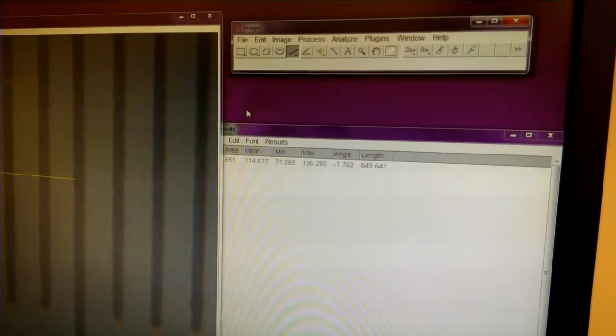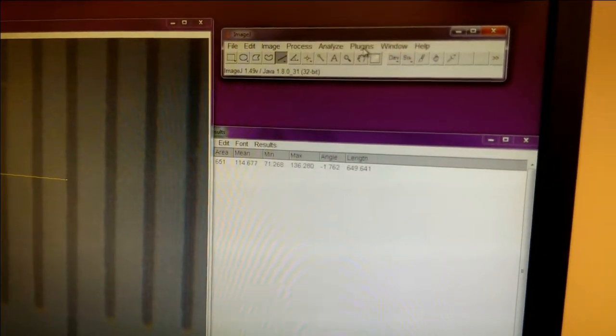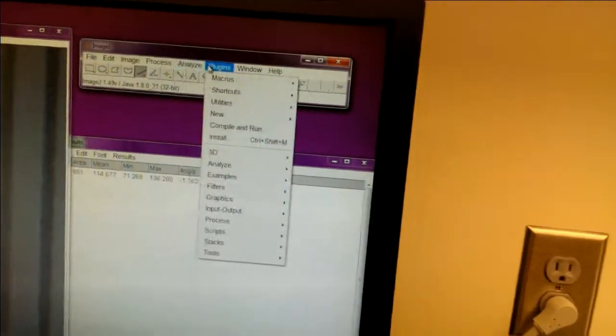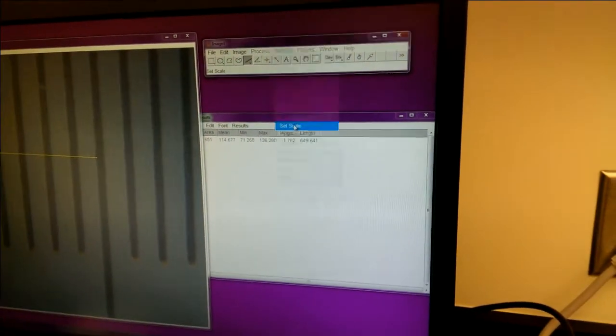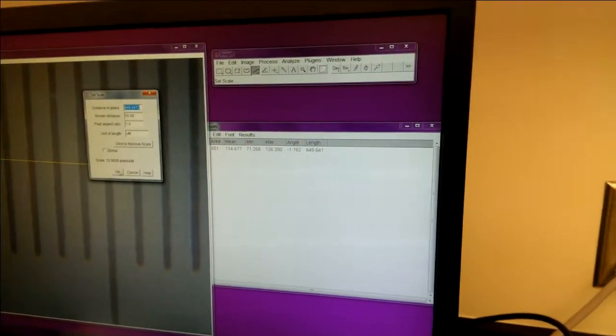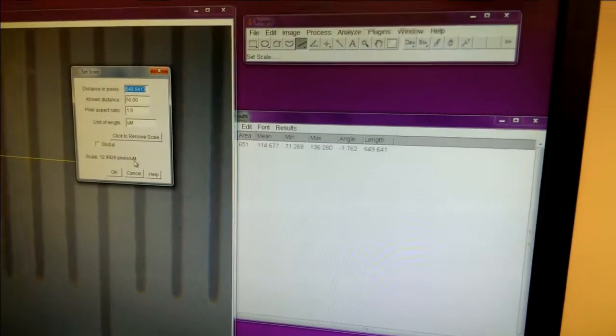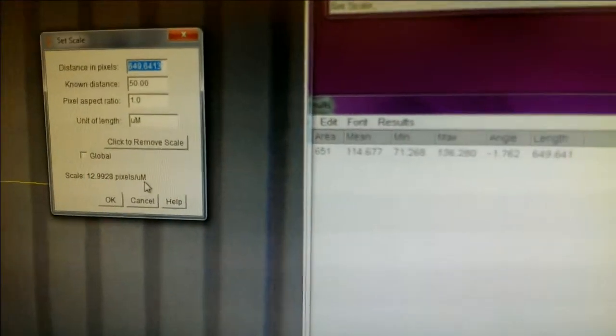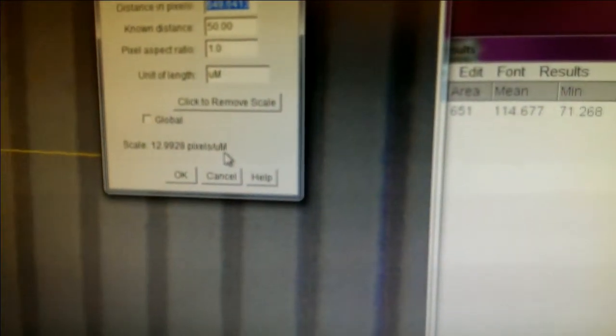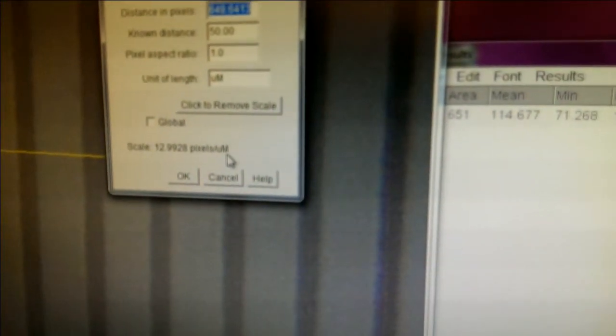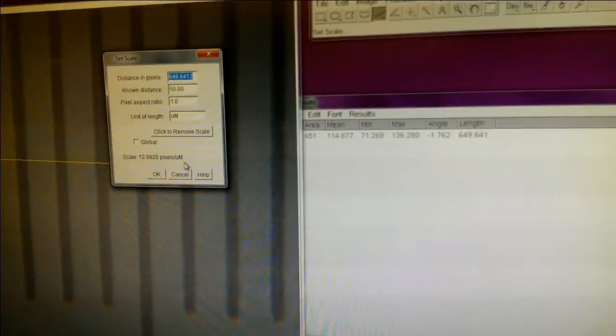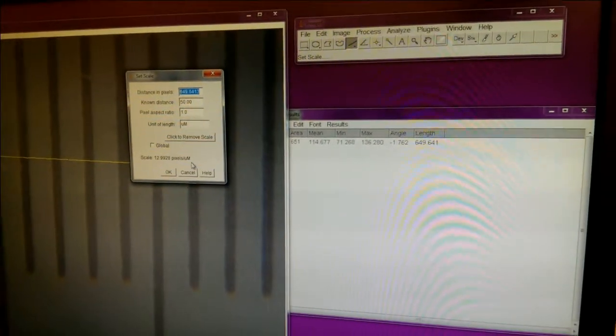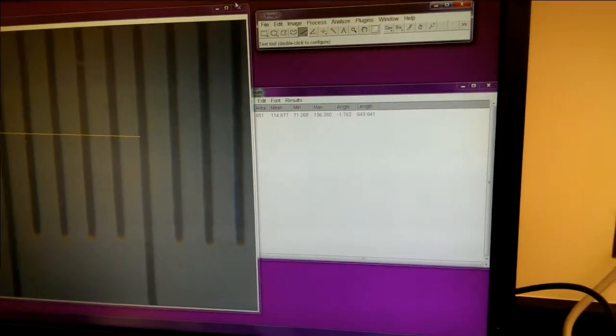So now it knows what your distance is, and if you go back into the same menu, it actually tells you that your scale is 12.99 pixels per micron, or 13 pixels per micron. So you might get a slightly different number, and that's okay, but you should do this calibration step.